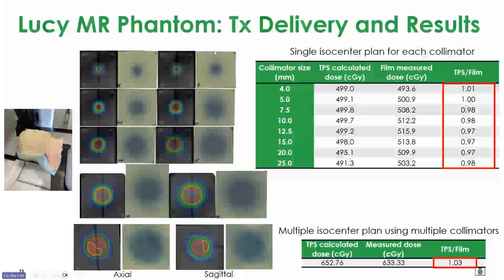And then the actual delivery. I put the phantom in the machine and inserted it in the cube. Each one has a film. I individually delivered from the 4 millimeter to the 25 millimeter collimator plan. And then film calibration was done, I read the film, and compared the TPS calculated dose and the film measured dose. Same thing for the multi-isocenter plan. I irradiated the axial plan, put the film in the axial axis and sagittal axis, and compared the measured dose. It was all within 3%, which is pretty good.